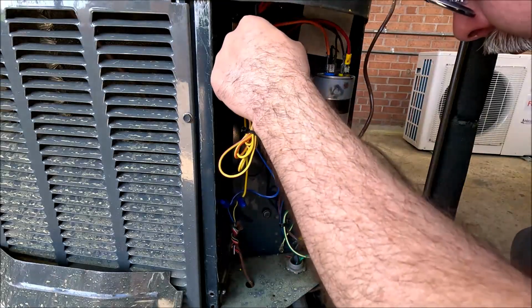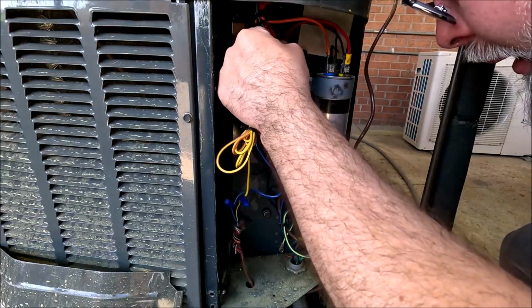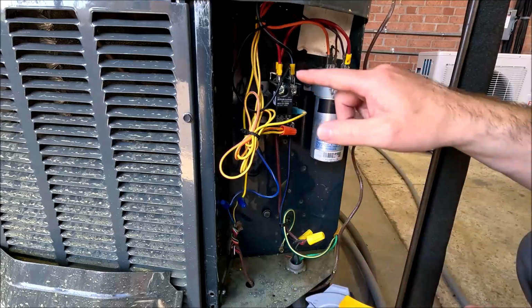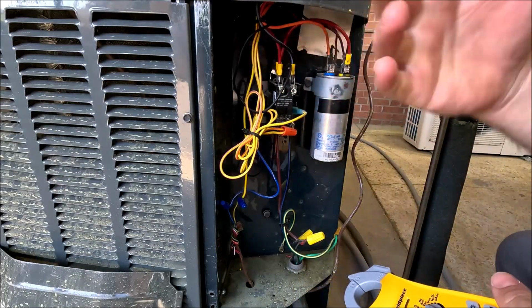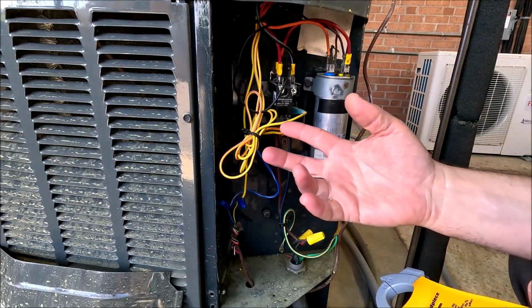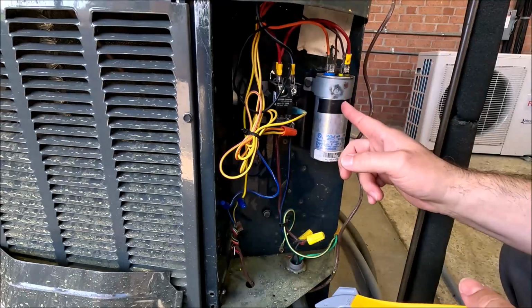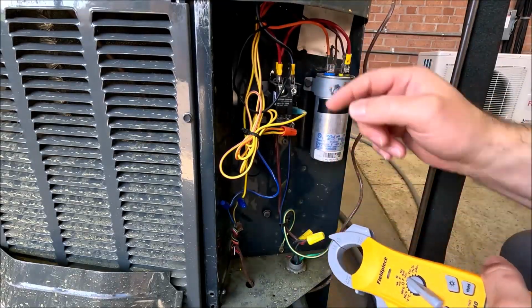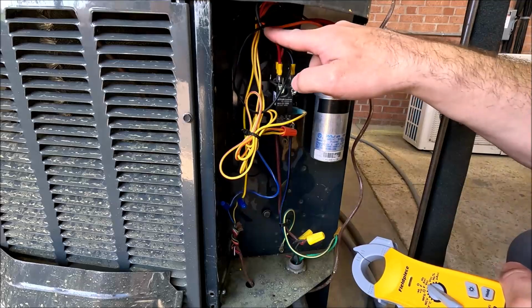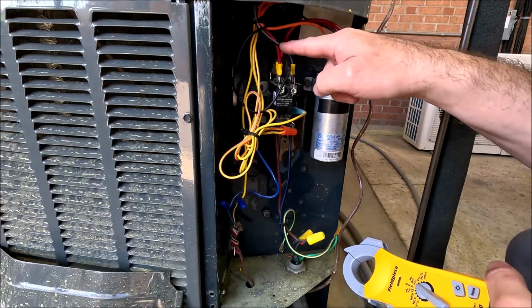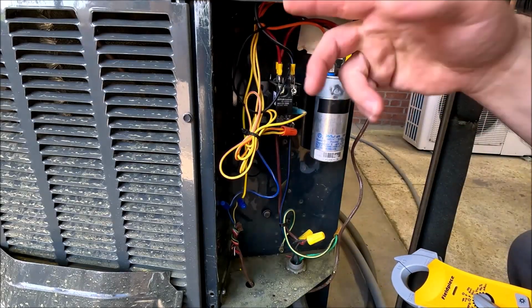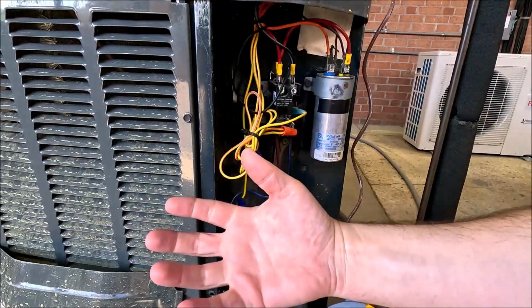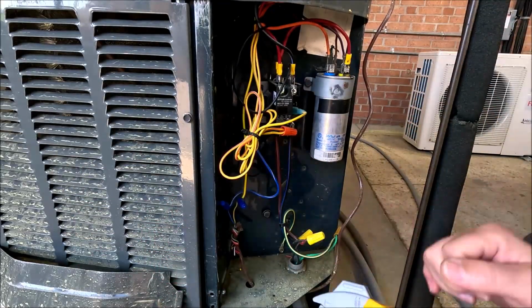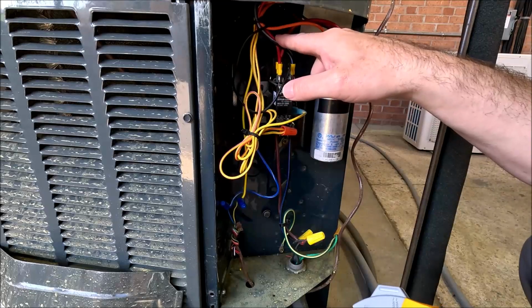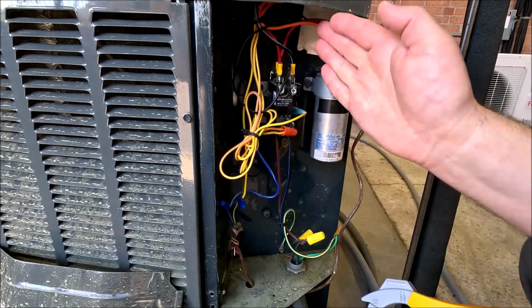So we had a loose connection here, and that red wire actually pulled off. So I lost the L1 to my run winding and also into the capacitor for the start windings. But what I was trying to tell you is this black wire right here would be my compressor, the return from the common terminal back to the power source. Now, if it's a tight connection, I still know that it's on this side.